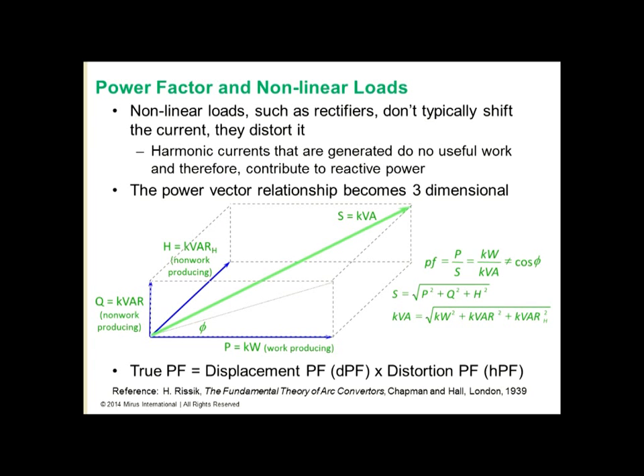So when we have nonlinear loads, the harmonics that they generate affect power factor. Typical nonlinear loads are rectifiers such as a variable speed drive. And these don't typically shift the current, but rather distort it. Harmonic currents that are generated do no useful work and therefore contribute to reactive power. The power vector relationship then becomes three-dimensional.